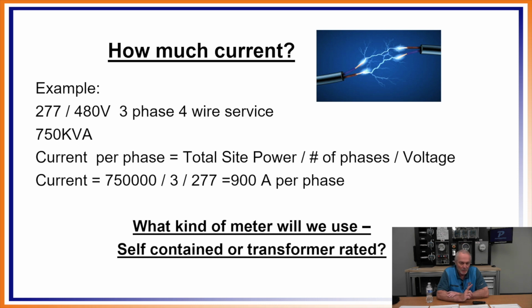If you're looking for the current per phase, which is what we need to find, you take the total site power divided by the number of phases divided by the voltage. In our example here, it was 750 kVA, so you have to multiply by 1,000. That's why it shows 750,000, because it was kVA. You add the 3 zeros there because the K is a factor of 1,000. So I've got 750,000 divided by 3 divided by 277, which gives me 900 amps per phase.